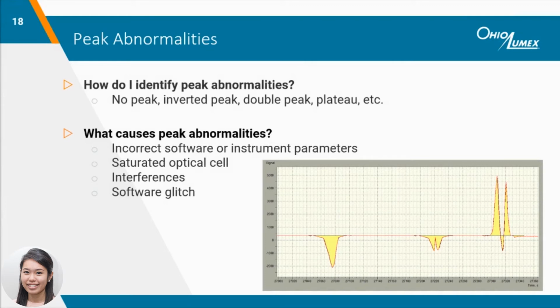Some peak abnormalities present themselves with the first mercury peak, but others happen sporadically and are sometimes unavoidable. Intermittent peak abnormalities can occur when the optical cell is oversaturated with mercury beyond the calibration range, or when loading a large amount of data in the software, like the measurement database, while a peak is eluting. It's a good laboratory practice to view the entire peak after it elutes to confirm the peak was not compromised. Avoiding the use of any program features during analysis will help prevent glitches as well.